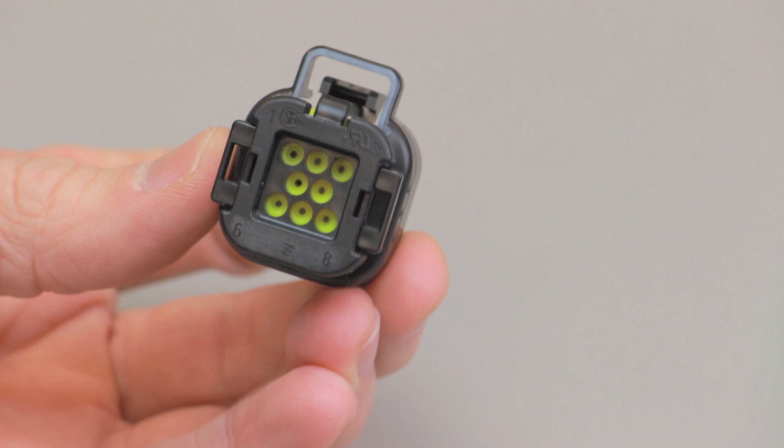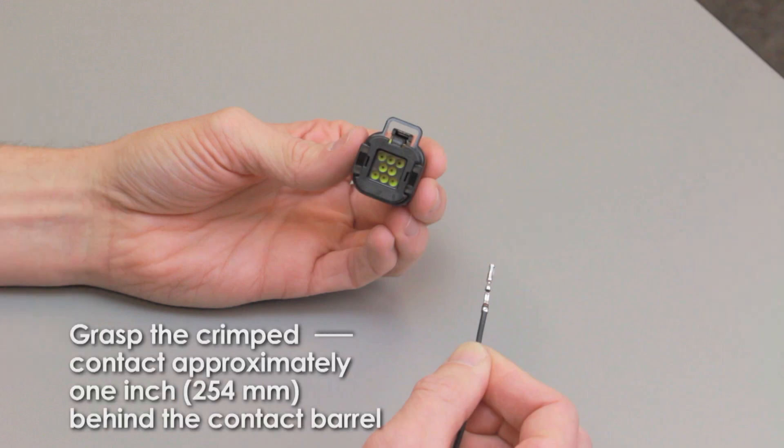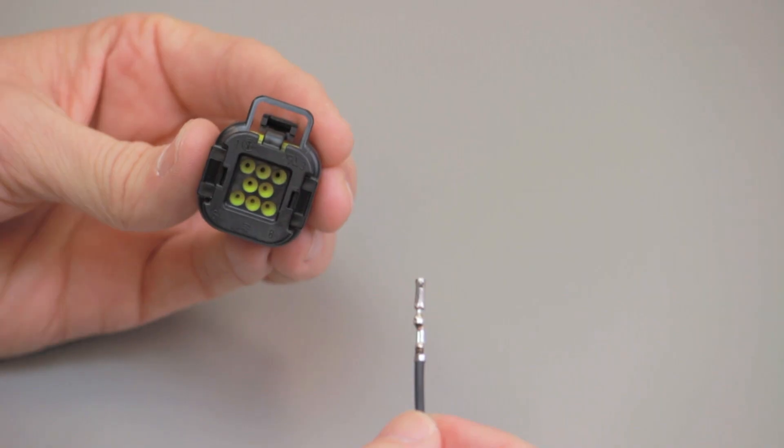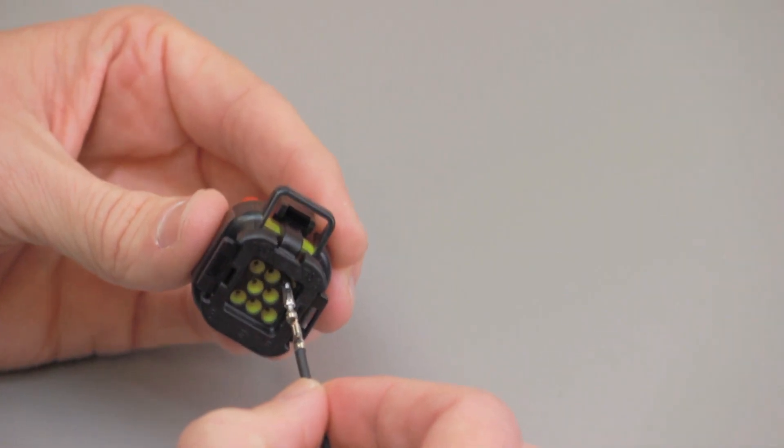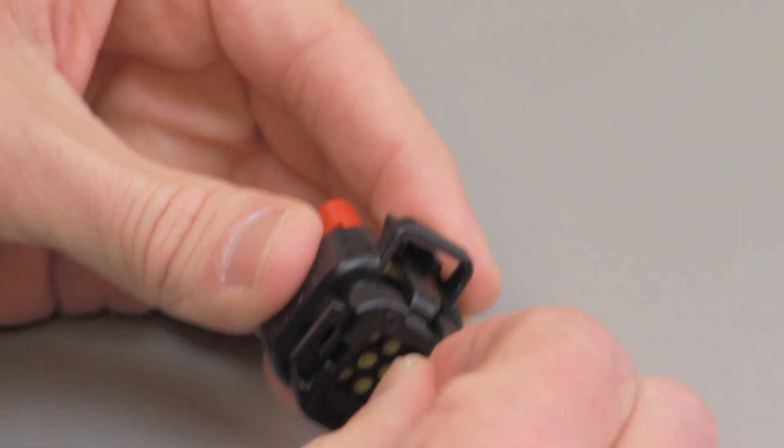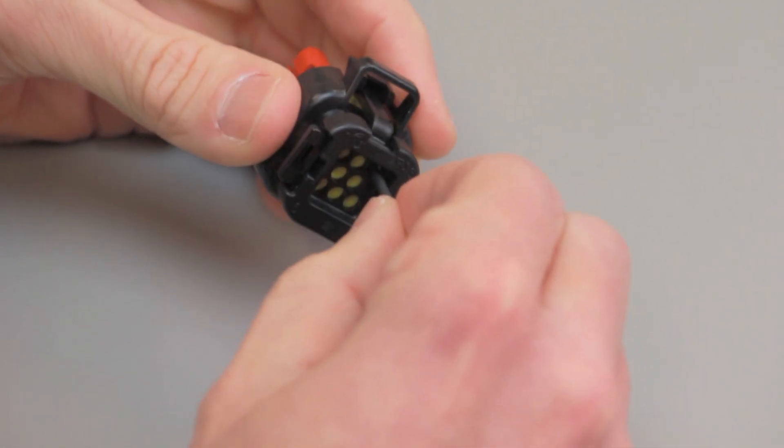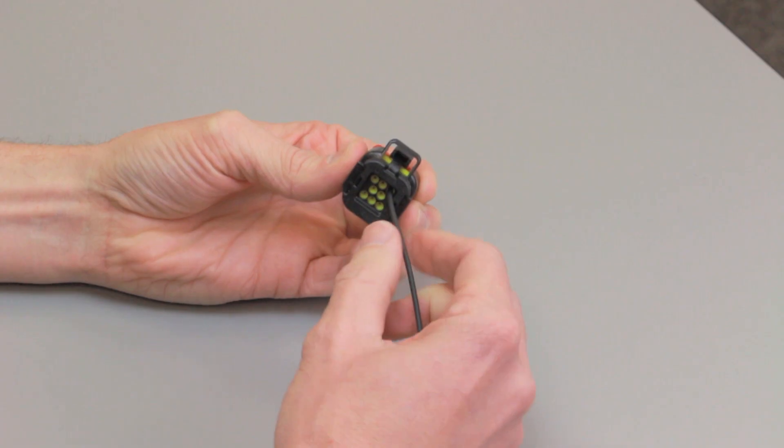Empty cavities will remain sealed. Grasp the crimped contact approximately one inch behind the contact barrel. Insert the contact into the connector cavity until you hear and feel a click. A slight tug will verify the contact is locked in place.